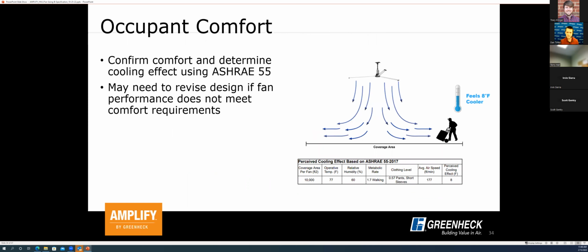So the next step in the design process—we've identified our building type, application, and performance requirements, and what we care about. Next is really starting to look at whether we're maintaining comfort in the space. This is where the ASHRAE 55 standard comes into play, along with data from AMCA-certified performance information and from fans tested according to the ASHRAE 216 standard for air speed. That's where this information helps ensure we're compliant with ASHRAE 55 and providing a thermally neutral, comfortable space.